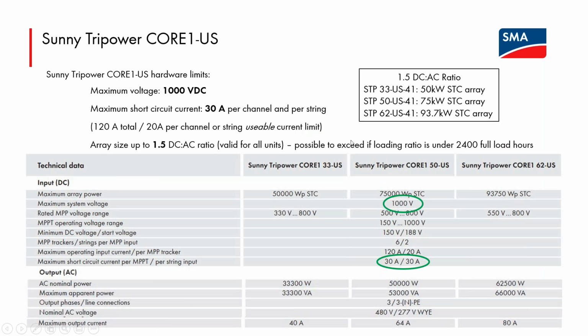I'm sorry, this is a very boring slide, just data sheet information. We're showing the top part of the data sheet for the 33 kilowatt, the 50 kilowatt, and the 62.5 kilowatt models of the CORE1 line. The two values circled in green on this slide show the maximum operating voltage for any model of the CORE1. That is 1,000 volts DC, so that would be the maximum voltage that any of the inputs of any of the models of the CORE1 can be exposed to at the coldest temperature for operation.